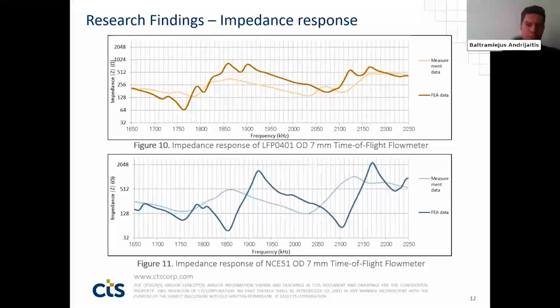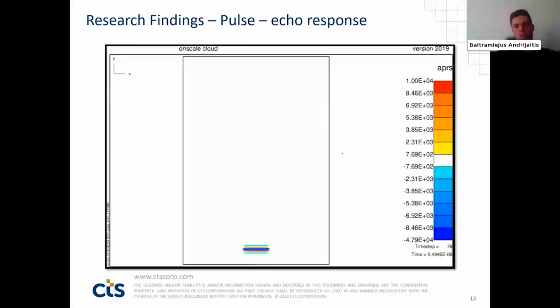So here, as well, we have a comparison of lead-free and lead-based transducers. Again, on the curves, we can see some differences. These differences could come from various sides: material metrics inaccuracies, quality of assembly, and differences in geometry of the ceramics, because in the real case we use ceramics with wraparound, and in the model we performed the edge-to-edge electrode. However, again, differences are not significant. It's up to 5%. So the model was considered good to continue.